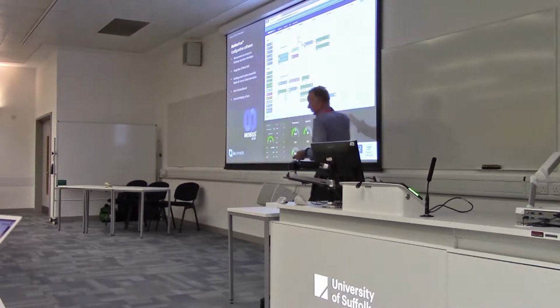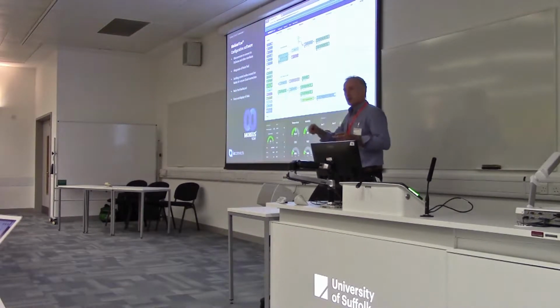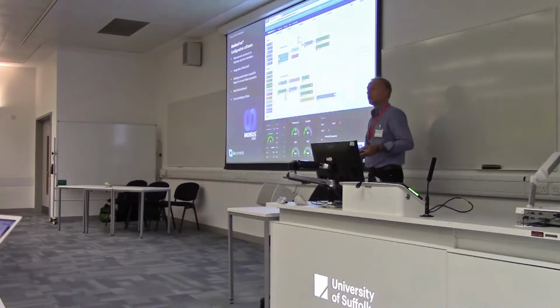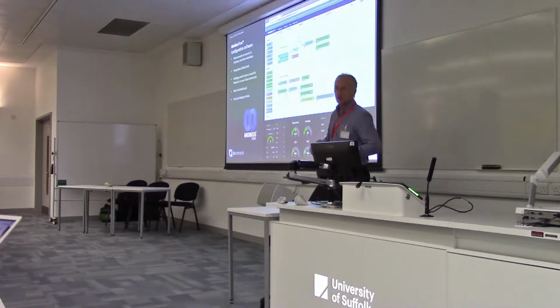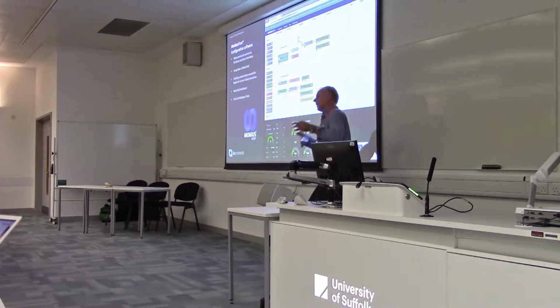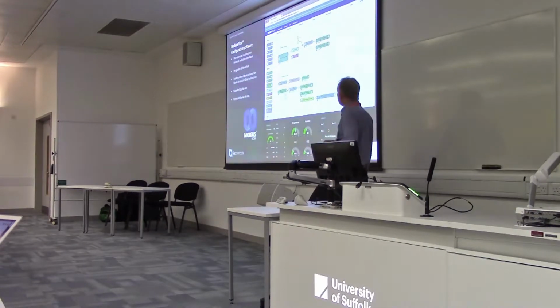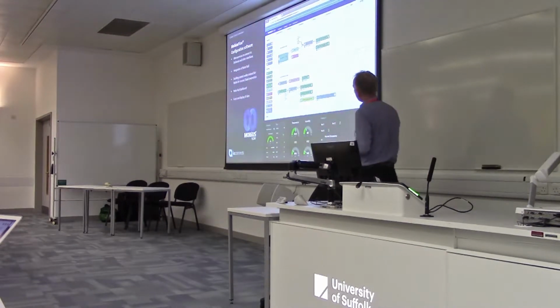In this instance, we used a product from IBM. They have a tool set called Node-RED, which is very much a drag and drop tool, and we can do very, very complex control systems now utilising just this. And the reason we do this is because when it gets handed over to the client for the OPEX phase, their maintenance teams can make these changes themselves because everything's represented in real words. They don't have to pay me hundreds of pounds to send my guy down with a laptop to make those changes because they don't understand it. And fundamentally, we think that's really, really important.